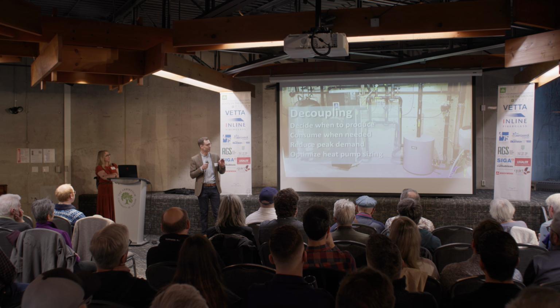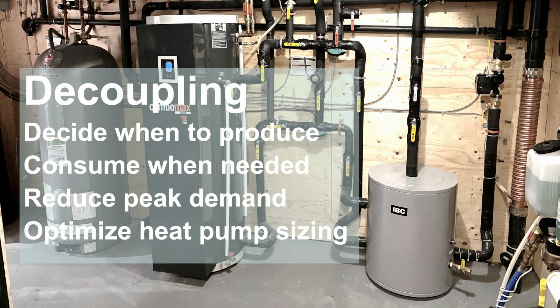They captured my feelings on this, which is that one of the biggest things we can get is decoupling. If you've got an air-to-air heat pump split system using refrigerant as the transfer mechanism between indoors and outdoors, when you need heating inside that home you need to run the compressor to meet that load in real time. There are some systems now with battery backup being tested in the Northeast states, from what I understand, so they can do a bit of load shifting, but we can do a lot more of it with hydronics. The idea of decoupling is separating when you need to consume heating and cooling in the house from when you want to generate it.